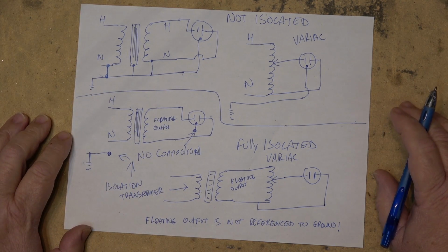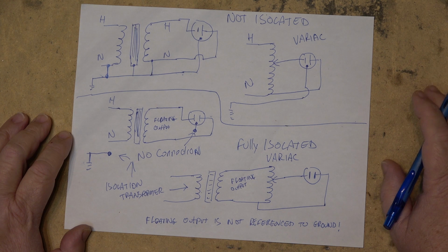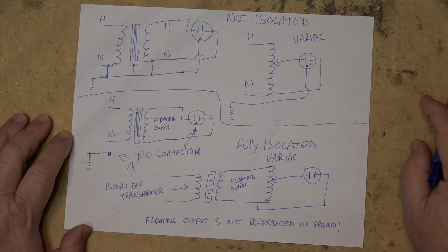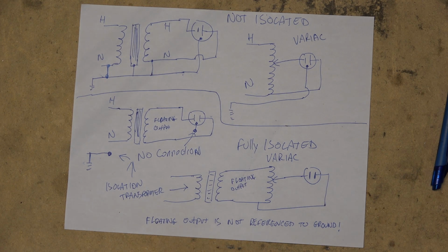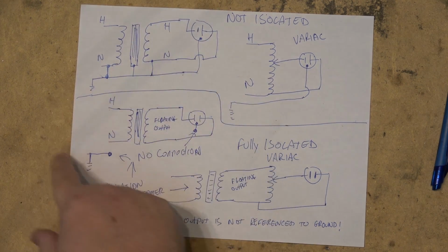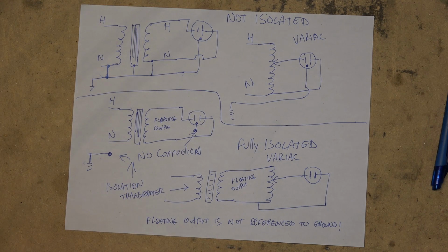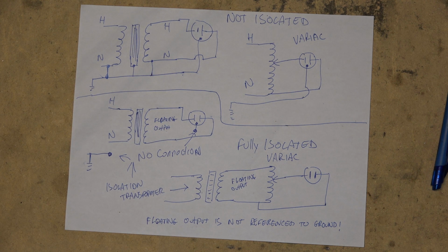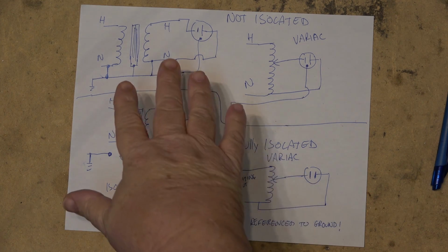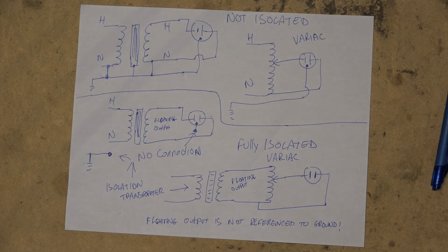On the many types of isolation transformers that have been sold on eBay, for example, they're not a true isolation transformer. They are in the sense that they're isolating, and they're this type, by the way. They are in the sense that they're isolating your equipment from the line coming in, the hot coming in from the street. These are typically what are referred to as medical isolation transformers or equipment isolation transformers.